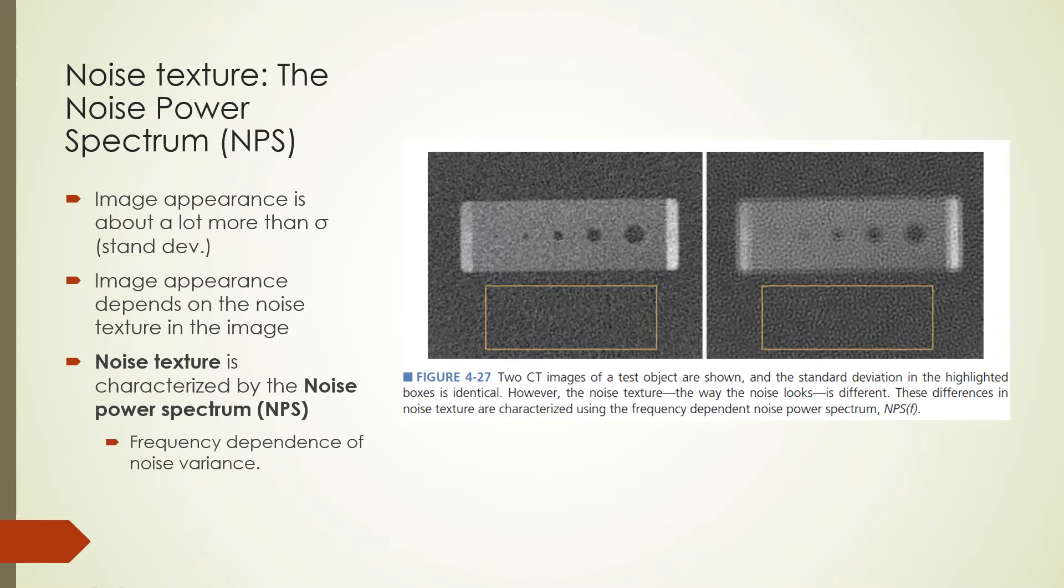We can understand the differences in noise appearance by using the noise variance, which is just the squared standard deviation. The frequency dependence of the noise variance is characterized by the noise power spectrum. Noise power spectrum of a system describes how well the system processes noise in an image. Noise power spectrum is important in CT, where different reconstruction kernels are used because each kernel either removes or preserves different frequencies of noise. So images can look different even if the noise magnitude is the same.